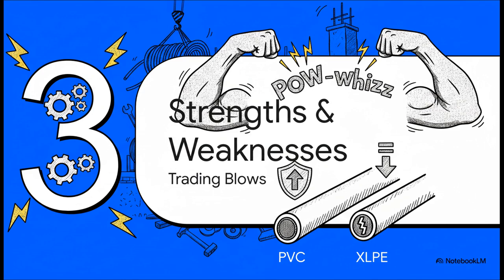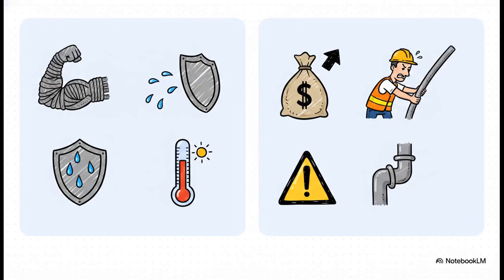We've seen the raw numbers, but how do these materials actually handle the practical realities of a busy construction site? Looking at XLPE, its strengths are definitely those high-performance stats: high ampacity, immense thermal resilience, great moisture resistance, and a lighter weight that actually reduces the structural loading on cable trays. But the drawbacks are very real for engineers on the ground. For one, it has a much higher initial procurement cost.